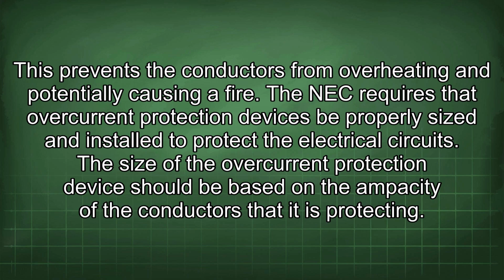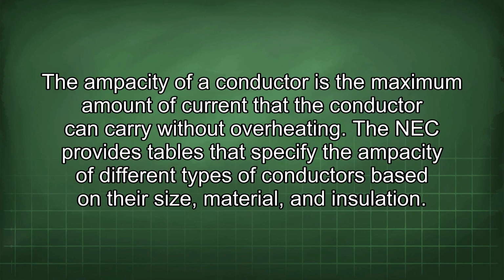The NEC requires that overcurrent protection devices be properly sized and installed to protect the electrical circuits. The size of the overcurrent protection device should be based on the ampacity of the conductors that it is protecting. The ampacity of a conductor is the maximum amount of current that the conductor can carry without overheating. The NEC provides tables that specify the ampacity of different types of conductors based on their size, material, and insulation.